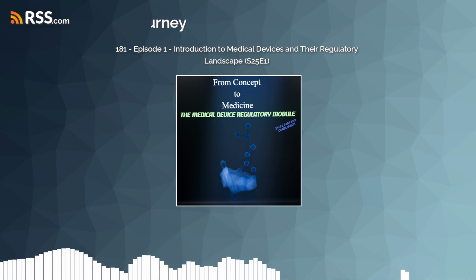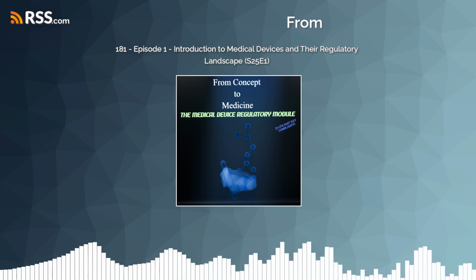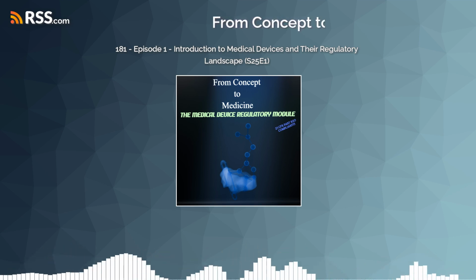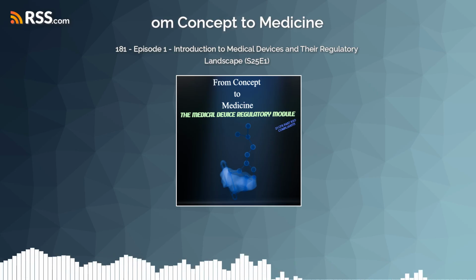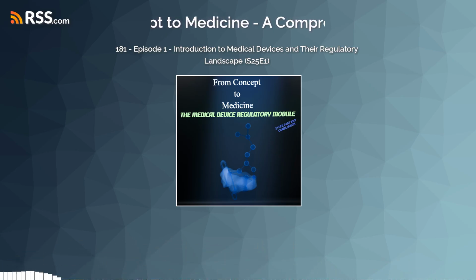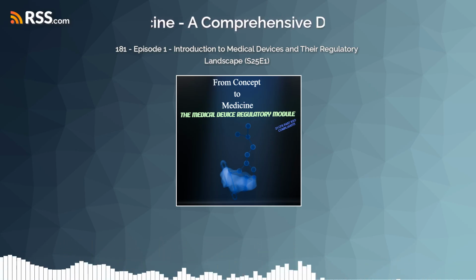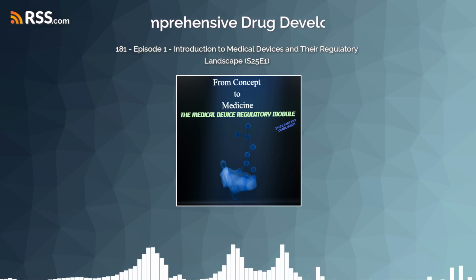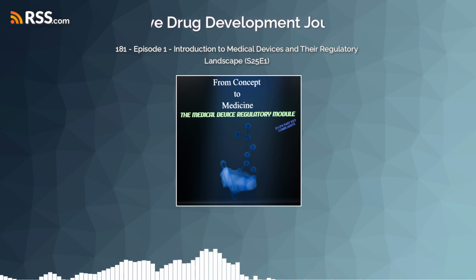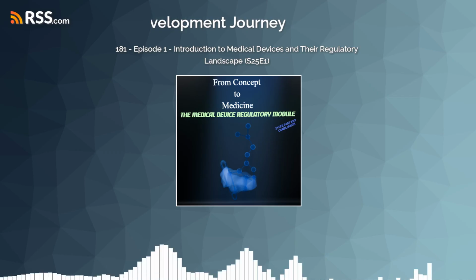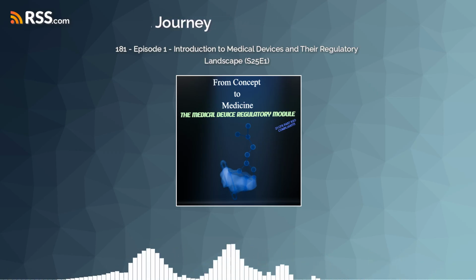So once a device is defined, classified, and that regulatory pathway is clear, especially for these higher risk Class 2 and 3 devices, what about the human studies, the clinical trials? When do those come into play? That brings us to investigational device exemptions, or IDEs. These are outlined in the regulations, specifically 21 CFR Part 812.